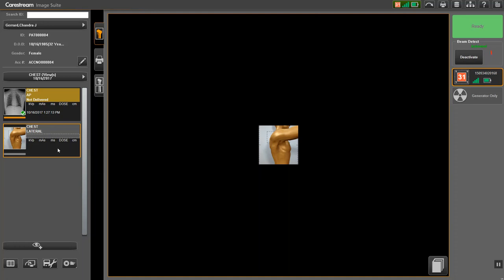You are now ready to position the patient for the next view. While you are positioning, the timer will continue to count down. If the timer counts down completely, the detector will be deactivated. Simply click on the Activate button to reactivate the detector.